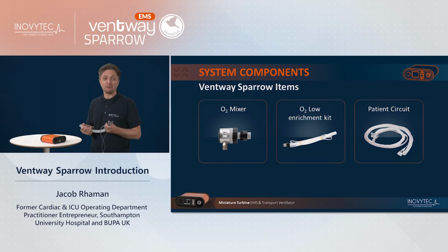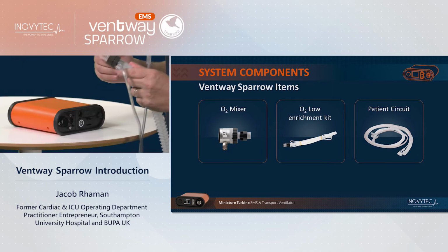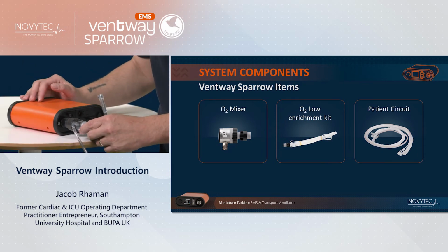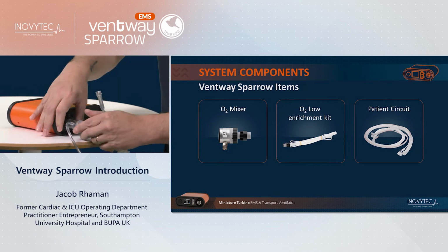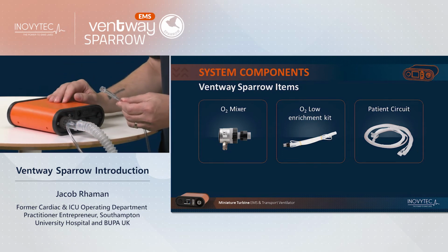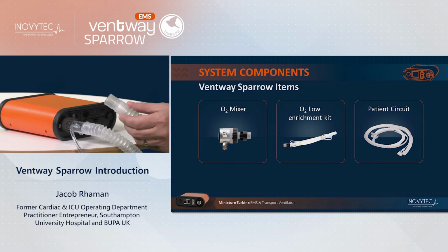3. The Ventway Sparrow also comes with a low-flow oxygen enrichment kit. This acts as a reservoir of air. When opened fully, this can contain up to 700 ml of air that can be supplied to the patient. When connected to the oxygen cylinder, the patient can receive up to 100% of oxygen. The end of the oxygen enrichment kit is connected to the air or oxygen inlet on the rear of the ventilator, like this. The thin tubing is then connected to the oxygen cylinder. The open end of the enrichment kit must remain clear and must not be occluded.